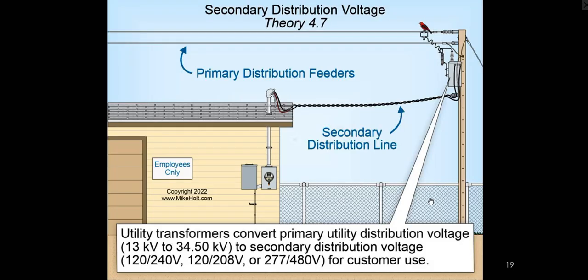Secondary. Utility transformers convert primary utility distribution voltage to secondary distribution voltage. And this is a great segment right here to make note of. The primary voltages that we deal with as electricians are what are termed nominal voltage ratings: 120/240 volts, 120/208, which is commonly three-phase, and 277/480 volts. Now, 120/240 is really the common voltage that you would see in residential applications. 120/208 would be oftentimes a three-phase application in a commercial setting, and 277/480 volt is kind of in the same sector there, but also in the industrial sector.